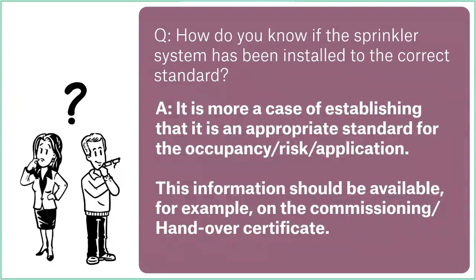But again, if the building is going through a period of change, change of ownership or being refurbished, then obviously I would recommend that be done as a matter of course, to overhaul the sprinkler system and bring it up to the latest standards, which probably wouldn't be a great deal of cost. Because the pipe and the actual distribution would be okay. You might want to change the sprinkler heads, but really it's going to be down to the installation control valves and the water storage that may need to be adjusted. Life safety as well. So again, if your sprinkler system is being used for life safety, does the code standard back that up as far as being appropriate?